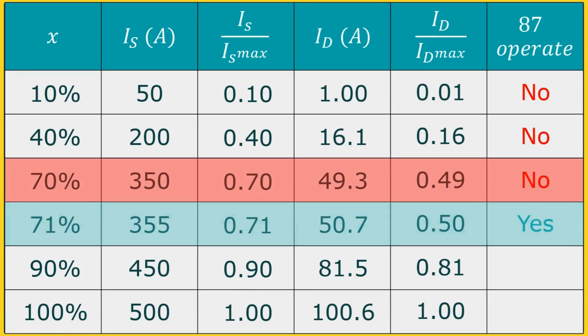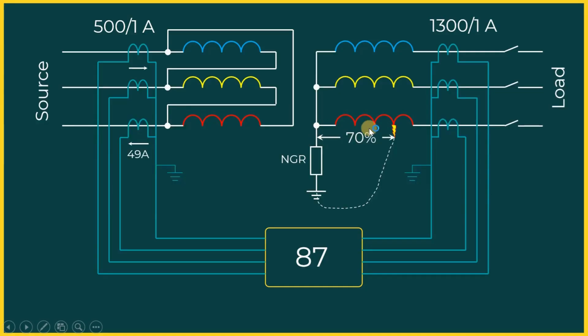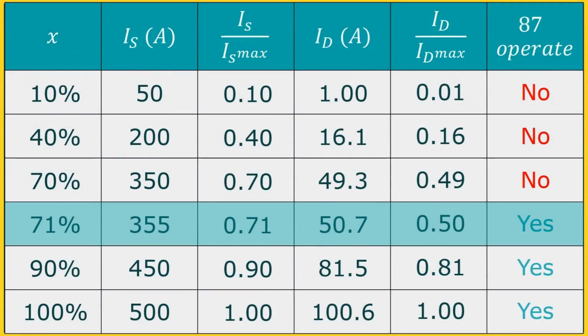Let us see this in the circuit drawing. From the neutral point up to 70% of the winding, if any earth fault occurs, the delta side current will be less than 50 ampere and hence the differential relay will not pick up. So only 30% of the winding is protected by the differential relay.